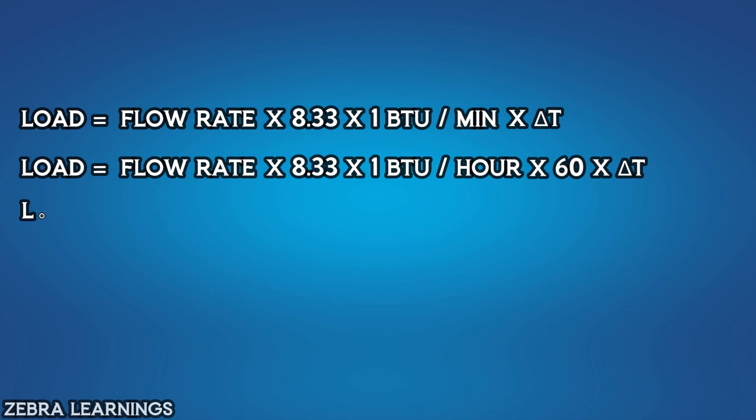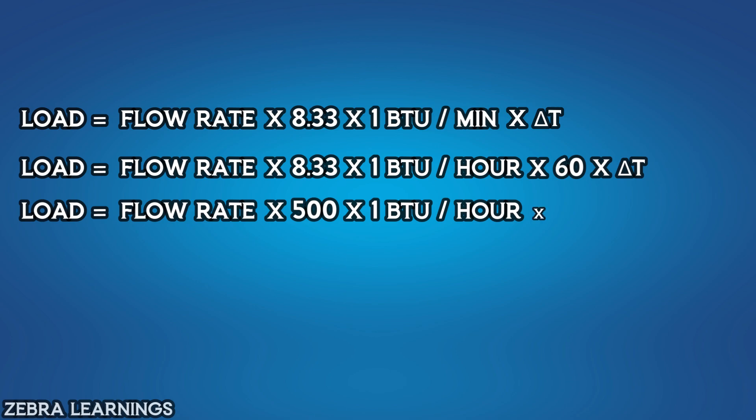So load equals flow rate multiply 500 multiply 1 BTU per hour multiply delta T.